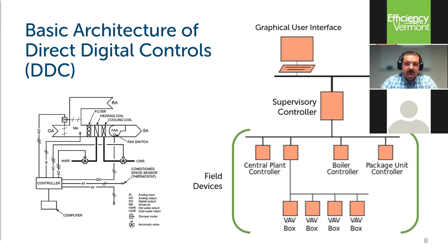That supervisory controller would then feed all those terminal controllers up to the server and the graphical user interface, the GUI. Typically with the servers, you would have the ability to bring in multiple supervisory controllers as your facilities got larger and your BAS systems got larger.